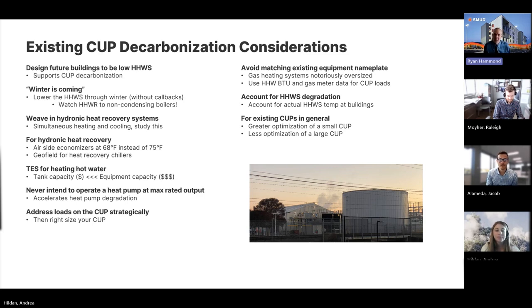Where possible, weave in hydronic heat recovery solutions. Why do I say that? You just purchased a precious kWh from your local electric utility to fire off your compressor. You fire off your chiller, you're getting single duty out of it: chilled water. You fire off your air to water heat pump, you're getting single duty out of it: heating hot water. If you can implement a machine like a 4-pipe air to water heat pump, a water to water heat pump, or a 6-pipe water to water heat pump, for that single kWh you just purchased, you're getting multiple duty out of it. You're turning a COP of 3 into like 5, 6 plus. It's amazing. So do that.